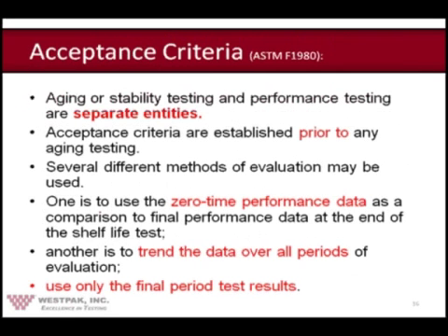Some cautions and notes are added in the ASTM F1980 document. These include the fact that aging studies and performance testings are separate entities. Well, of course they are. Who wouldn't think otherwise? Well, apparently someone did, or some people did, which is why it's specifically stated in this document.